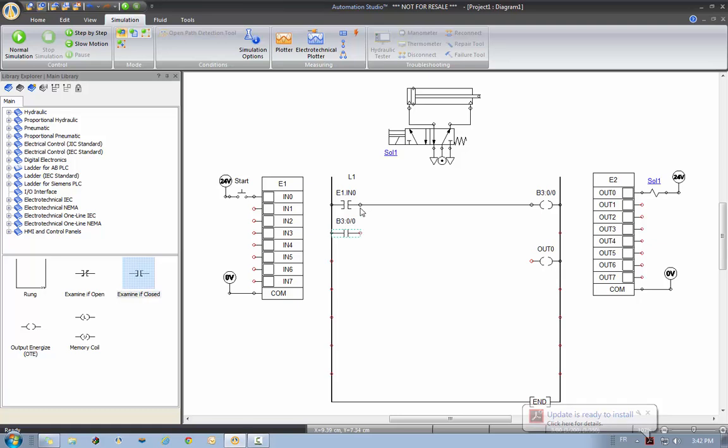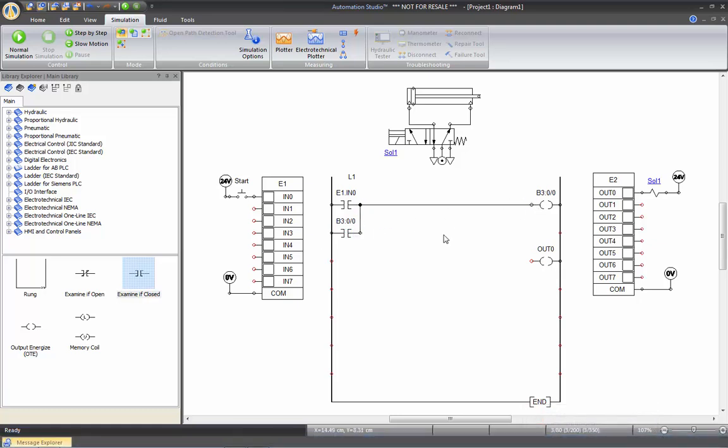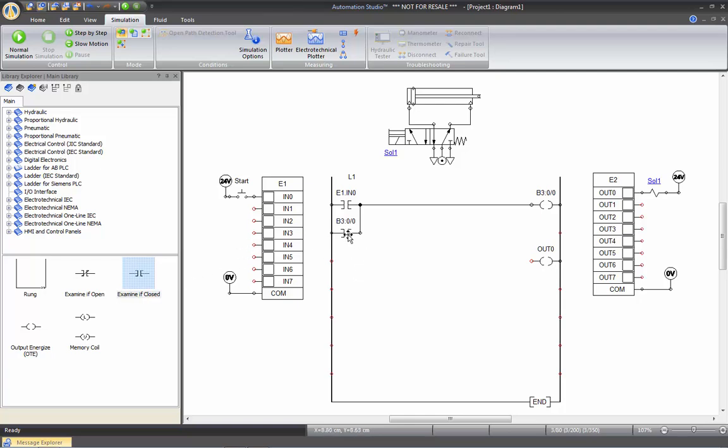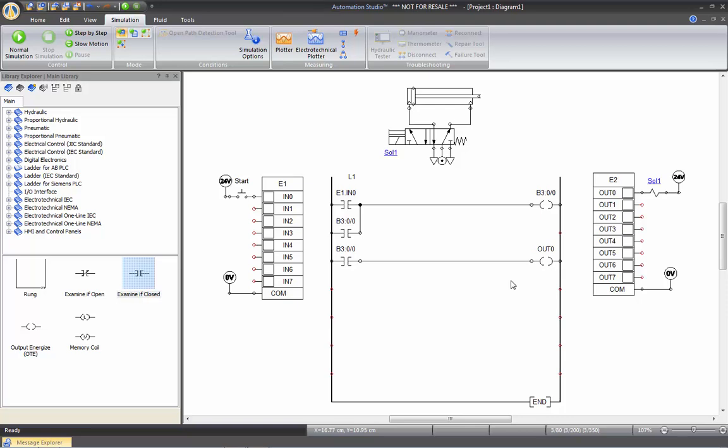And now I'm going to have a latch on my B3. So in order to trigger the OUT0, I'm going to have to put another B3 contact on this line. I can either take it from the library again, or I can simply hold the control key down and drag this contact down here, which I will link to OUT0. So now I will trigger the solenoid of the valve.